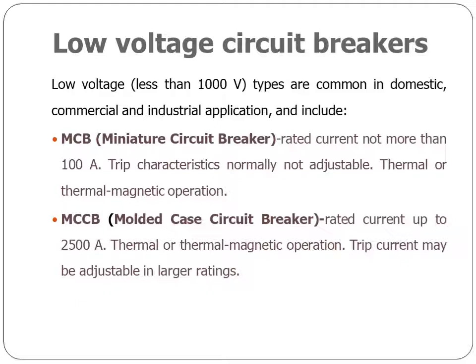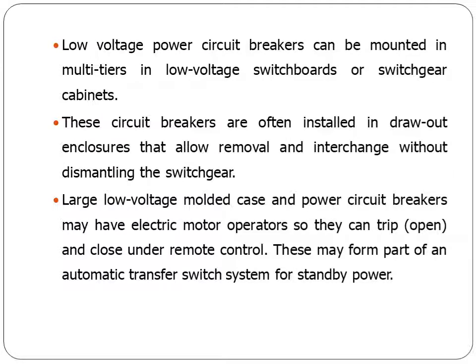MCCB, molded case circuit breaker. Rated current up to 2500 amps. Thermal or thermal magnetic operation. Trip current may be adjustable in larger ratings. Low voltage power circuit breakers can be mounted in multi-tier in low voltage switchboards or switchgear cabinets. These circuit breakers are often installed in draw-out enclosures that allow removal and interchange without dismantling the switchgear.